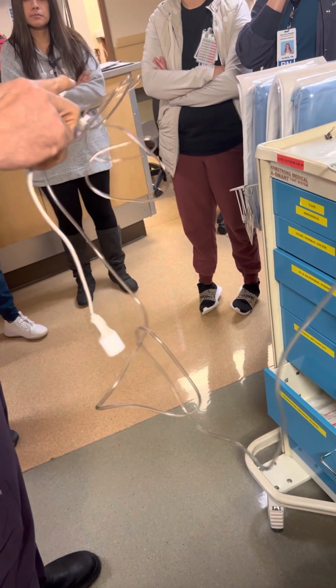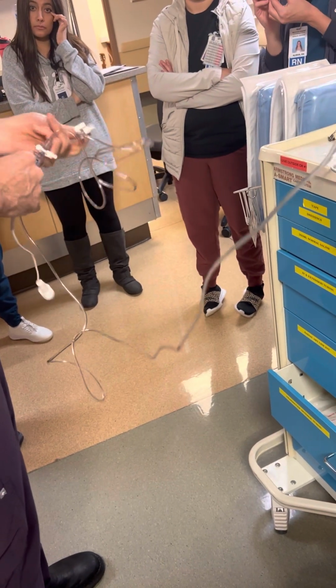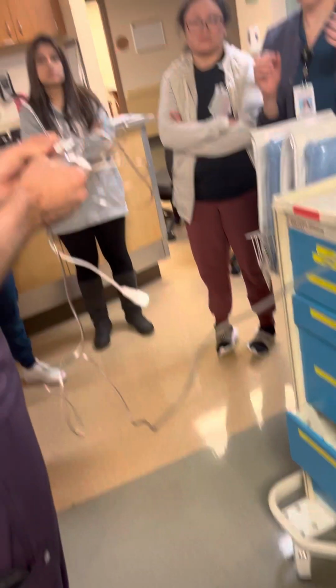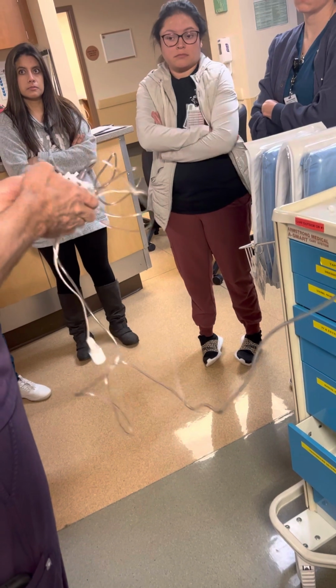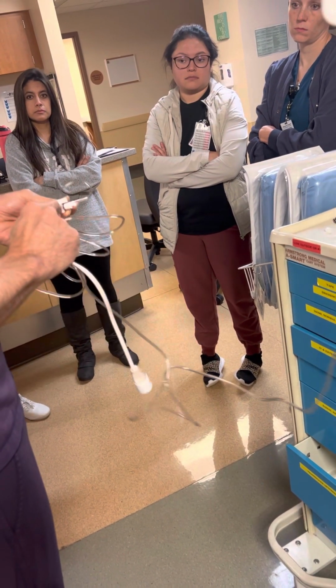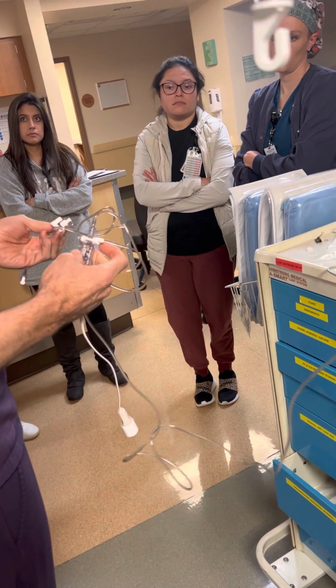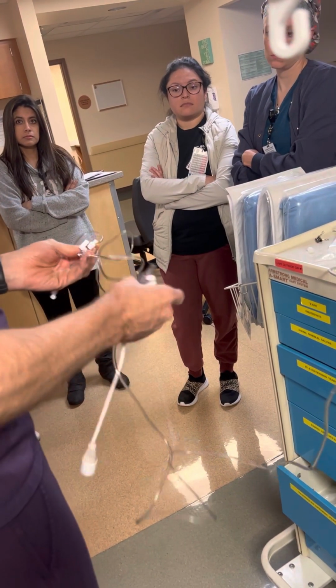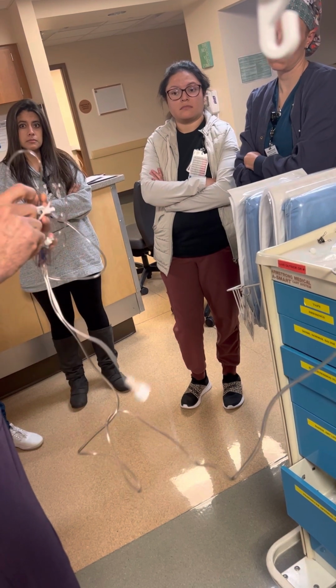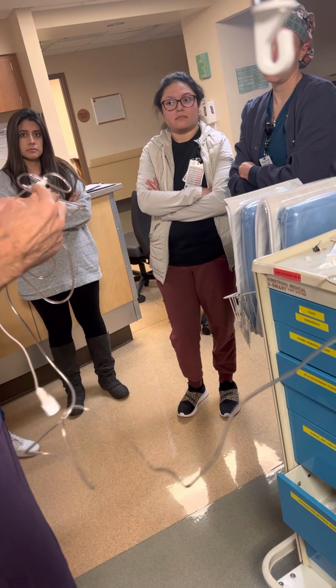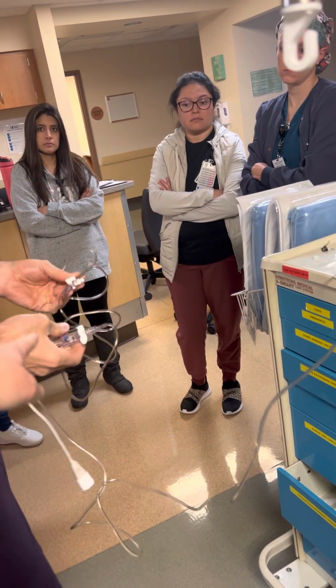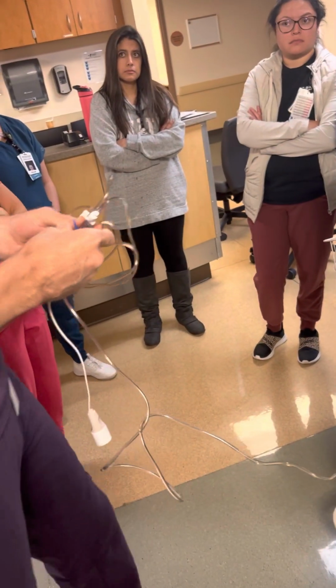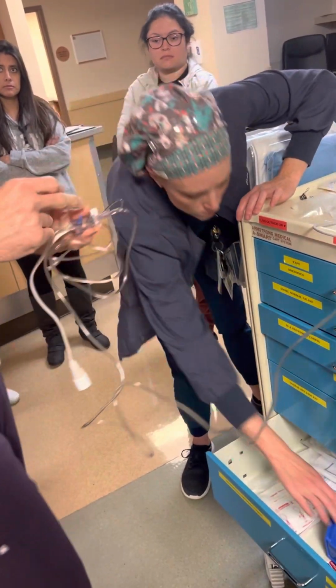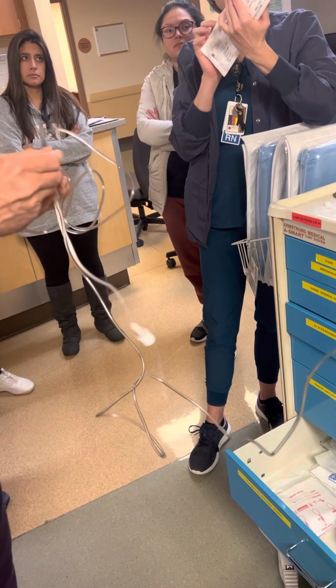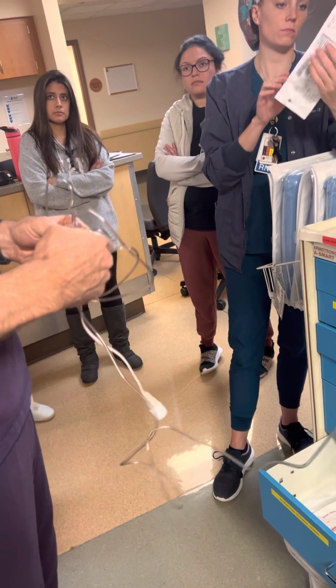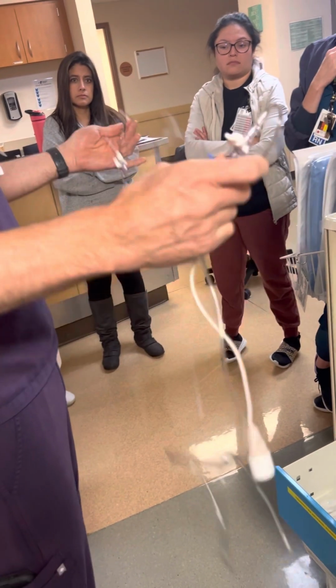No, that part of the line was not connected to where we flushed. The flush went through here, through there, right? I guess technically, yeah, we didn't use those ports. There's still air in there. And if we're using those, we're going to be drawing out the air that's in between the transducer and the patient. When you opened this tubing, was it already closed off there, or did you have to close them? This tubing, all I did was replace the cap. The line was open, but these are valves, so you can turn it off, and that becomes important. So we have the tubing, it's primed.